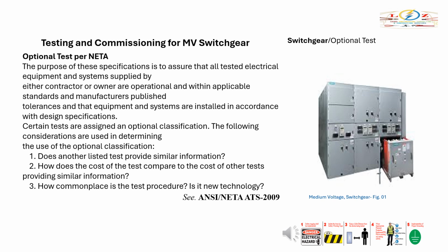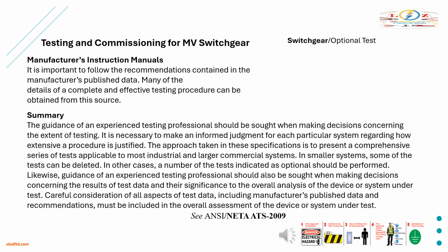1. Does another listed test provide similar information? 2. How does the cost of the test compare to the cost of other tests providing similar information? 3. How commonplace is the test procedure? Is it new technology? Manufacturer's instruction manuals. It is important to follow the recommendations contained in the manufacturer's published data. Many of the details of a complete and effective testing procedure can be obtained from this source.